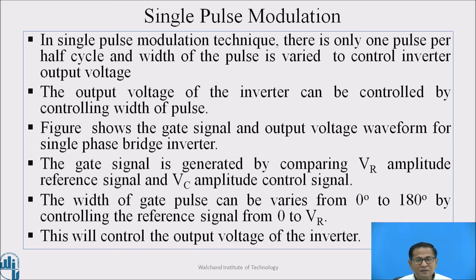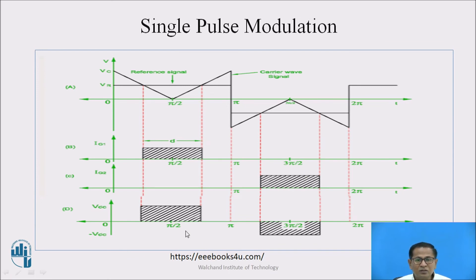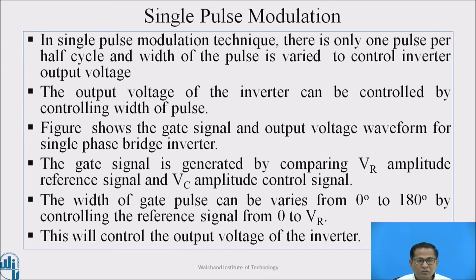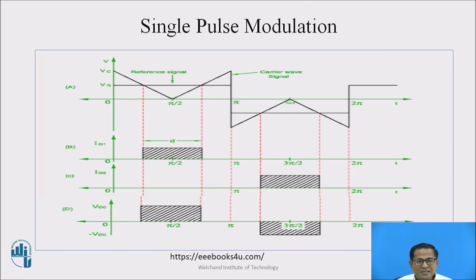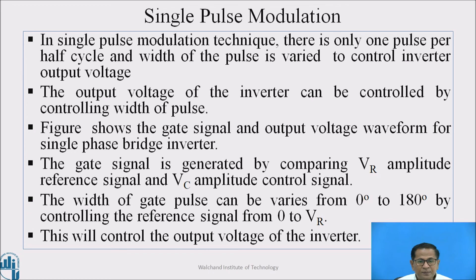The output voltage of the inverter can be controlled by controlling the width of the pulse. This figure shows the gate signal and the output voltage waveform for the single phase bridge inverter. These two are the gate pulses and this is the output of the single phase bridge inverter. In this methodology, the gate signal is generated by comparing the reference signal with a triangular carrier signal; at the intersection point the pulse is produced. The width of the gate pulse can be varied from 0 to 180 degrees by controlling the reference signal from 0 to VR, which controls the output voltage of the inverter.